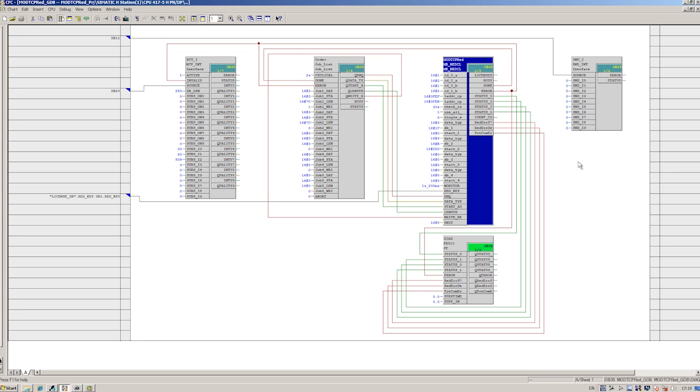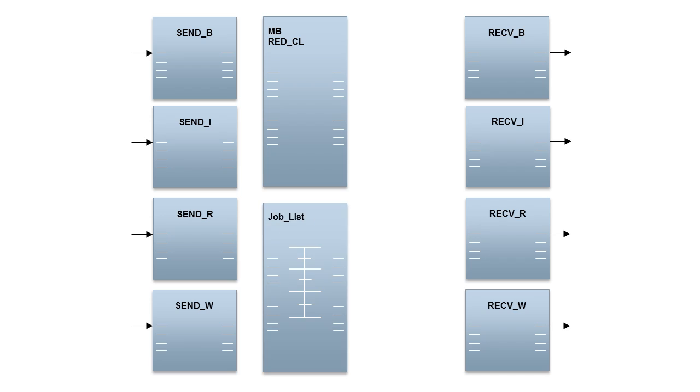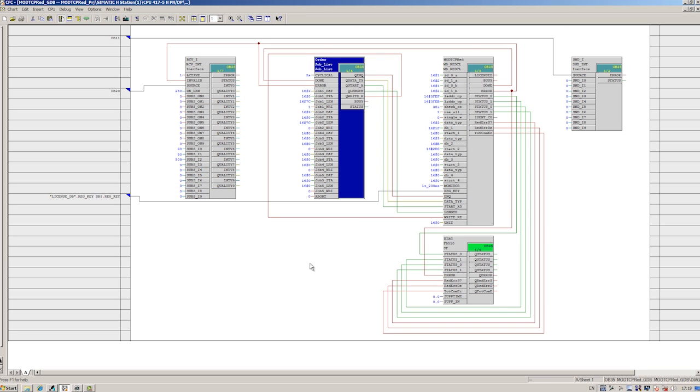The Modbus channel block coordinates the connections over which communication exchanges take place and is responsible for data storage. This block acts as an active partner and can coordinate a total of four jobs. The job list block provides a great deal of flexibility in parameterizing the different jobs. We can parameterize jobs individually and schedule the processing of the entire job list. All jobs can be interrupted and individual jobs can be temporarily skipped.